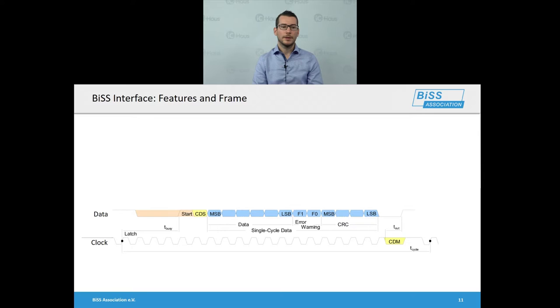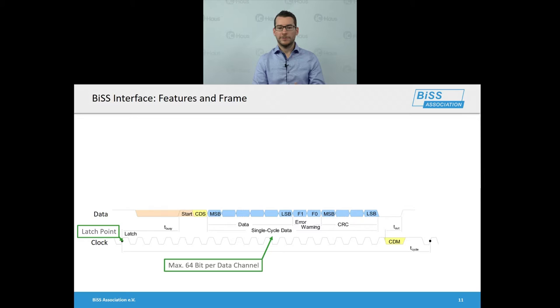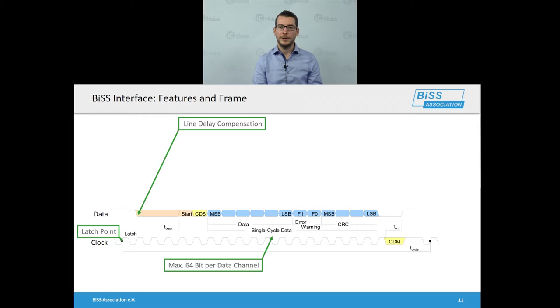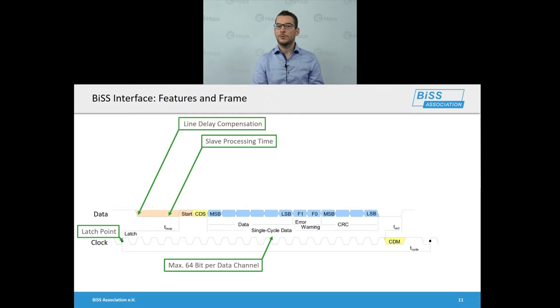Here you can see the BiSS frame. It usually starts with a latch point, which is a simultaneous data capture event for the whole daisy chain. There can be several data channels — usually one per slave — and each data channel can contain up to 64 bits of process data. The master is able to measure and compensate the line delay, enabling high transmission rates even on long transmission lines. The master can also consider the slave's processing time, so if the slave requires time after the latch event to prepare its process data, it can delay the start bit to request processing time.